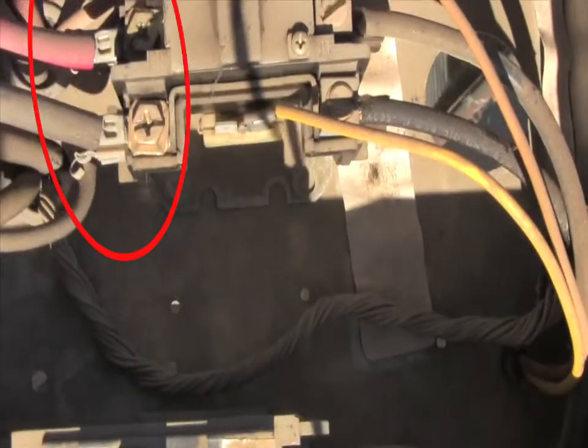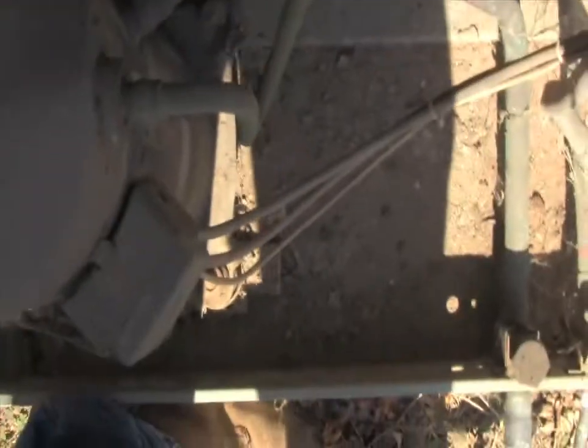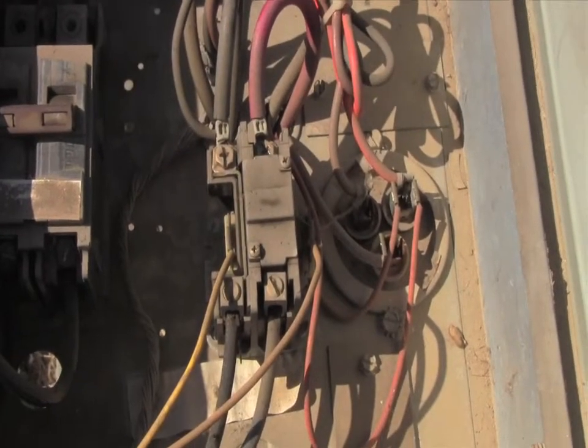This is the contactor right here, and this is the power inside. And this is the power out to the compressor, which is down here. And if you look, the wires come from the compressor and they go up through this opening right here. So if we come back up here to the top, I'm going to bring the camera around over to this side right here. We're going to take some initial readings on this unit.